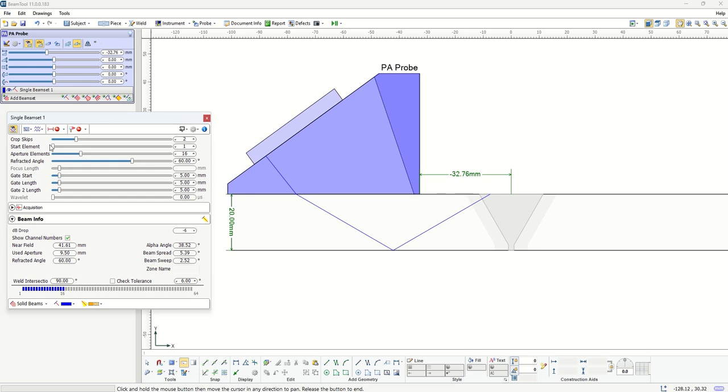In this case the start element is one, the aperture size is 16. You have information about the angle, gate length, gate start, gate end, and a tab that gives you all the information with respect to the beam that you have.